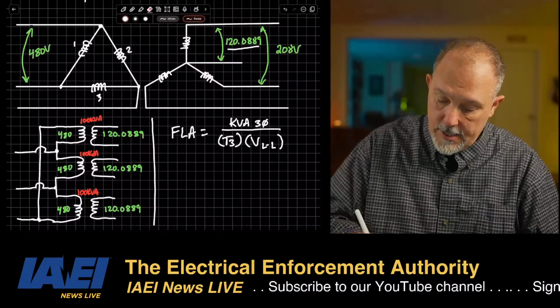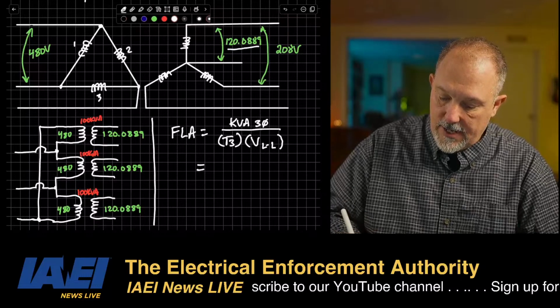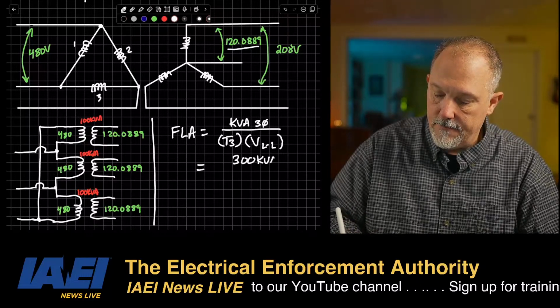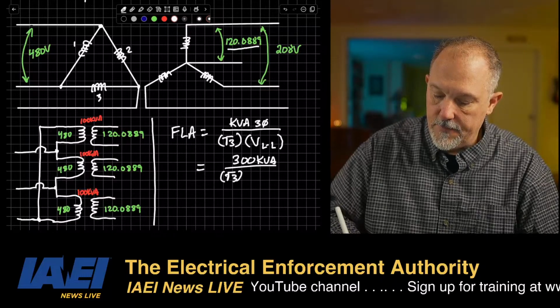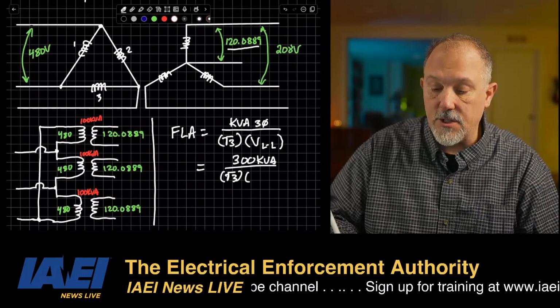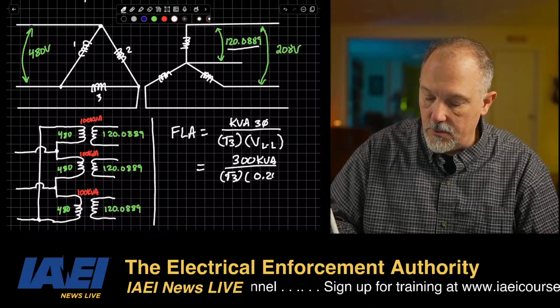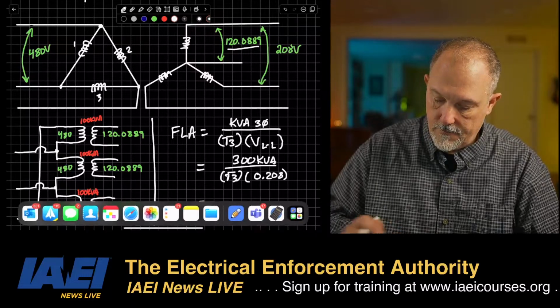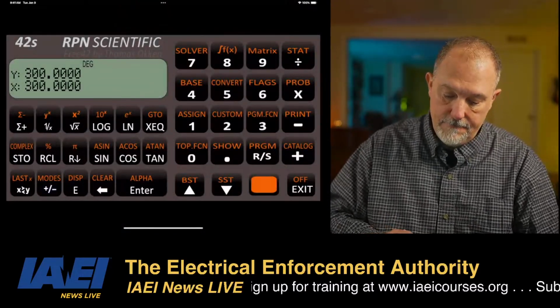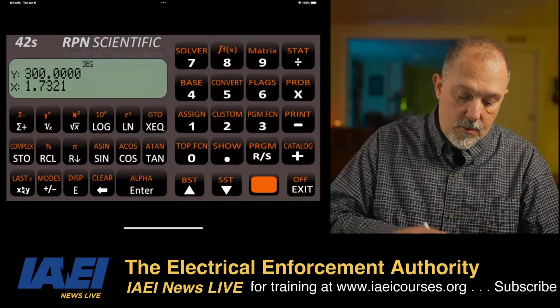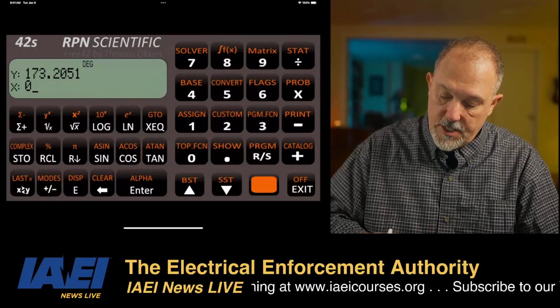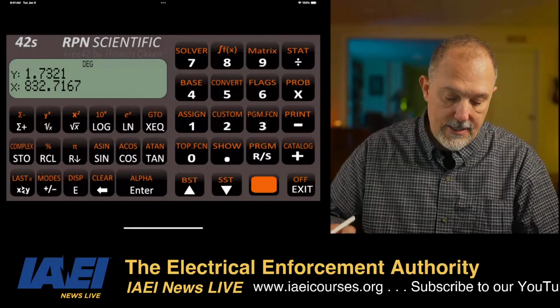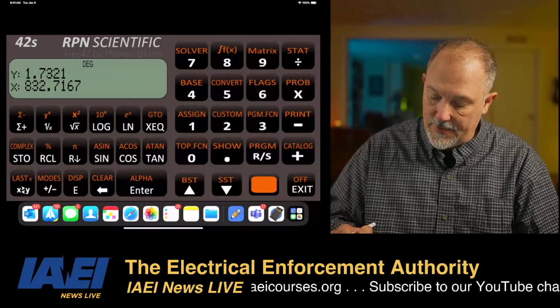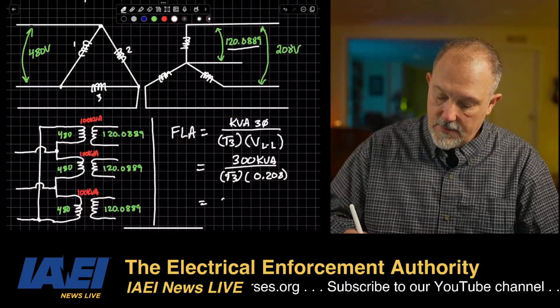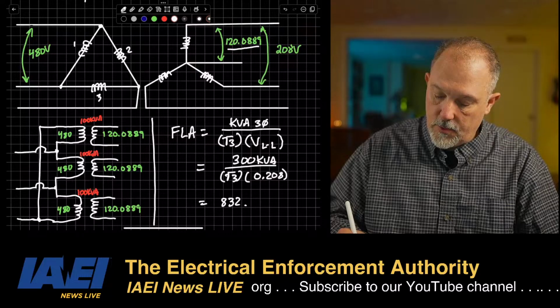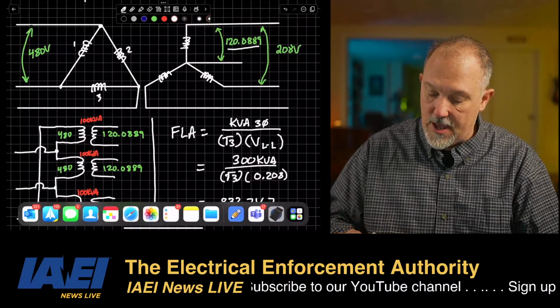All right, so if I'm working this out, I've got 300 kVA divided by the square root of 3 divided by the line-to-line voltage on the secondary, kV, is 0.208. So I got 300 kVA, 3 square root divide, 0.208 divide, 832.7167. Let's double check my math.